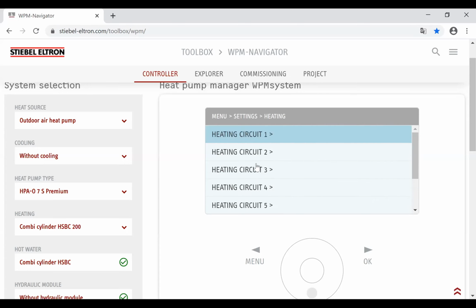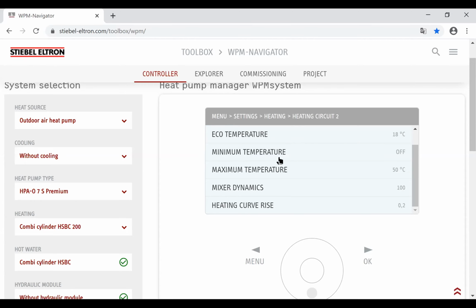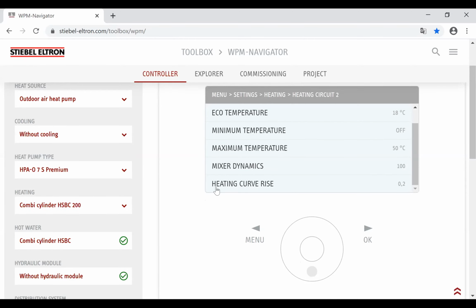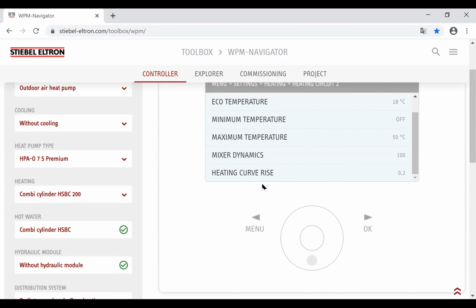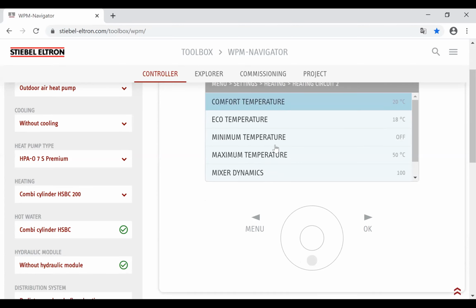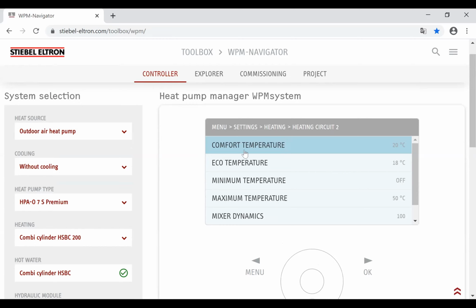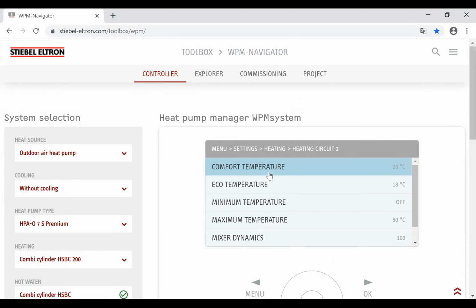So if we're just doing a heating system, we could, if we want, have no controllers inside the house at all. No controllers. We can look at each individual circuit and set them all up on their individual heat curve. That way we're just adjusting the temperature going to that heating circuit based on whatever's happening outside with the temperature. Now, you may ask a very sensible question. How can you set an indoor temperature then? If there is no indoor temperature sensor, how does it know? It's doing a calculation. That's all it is.